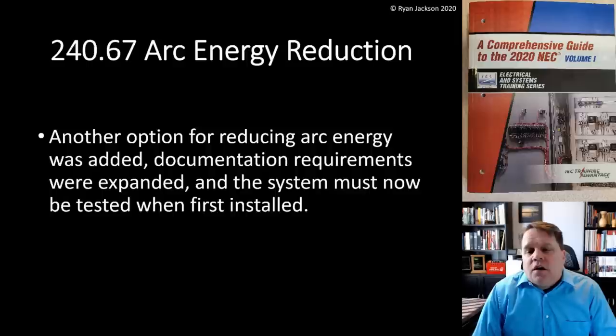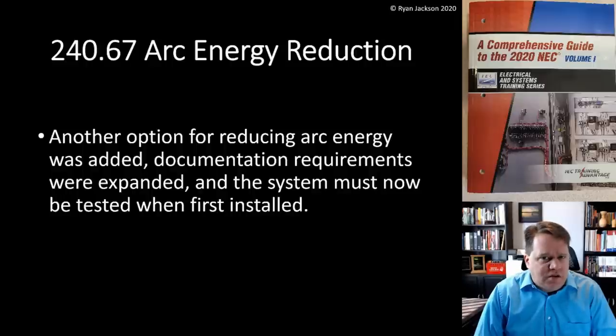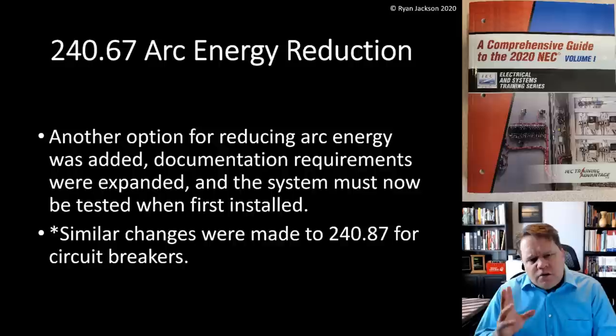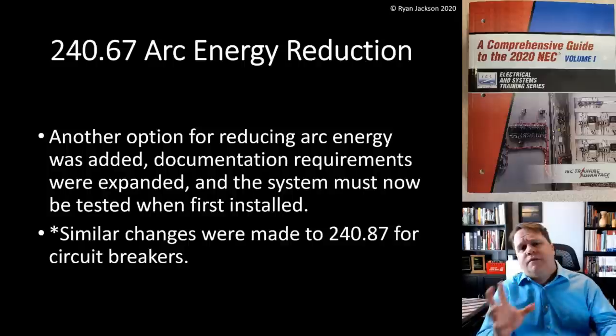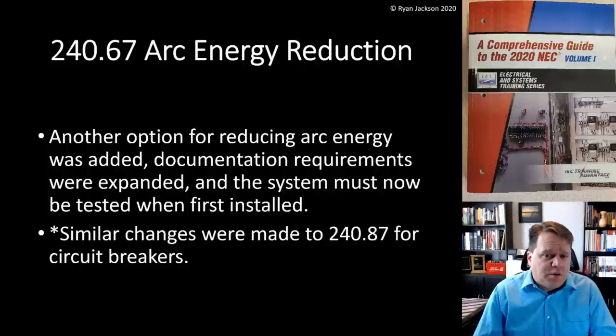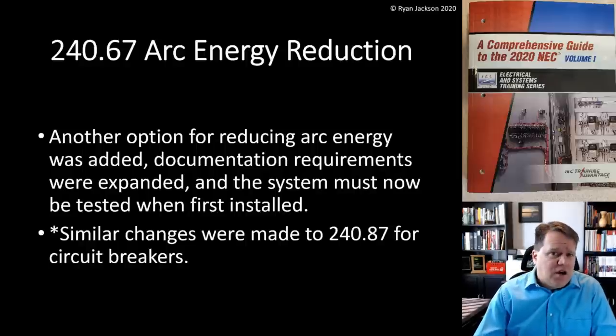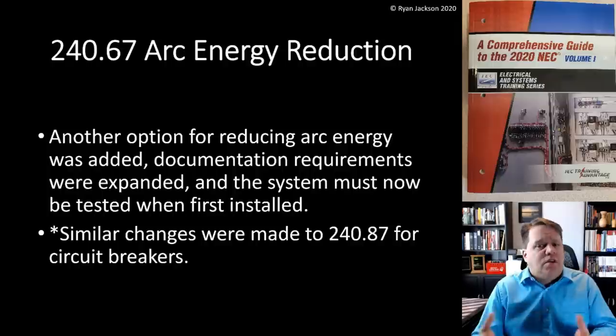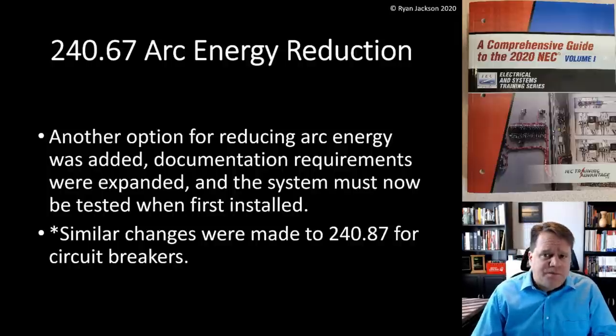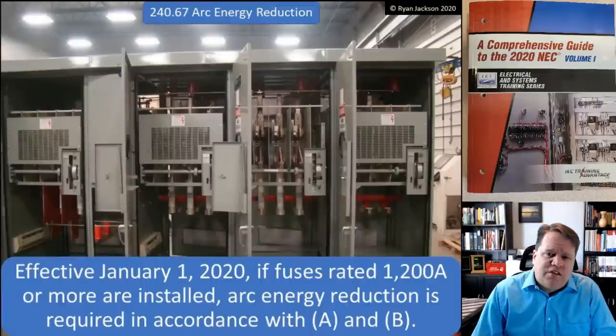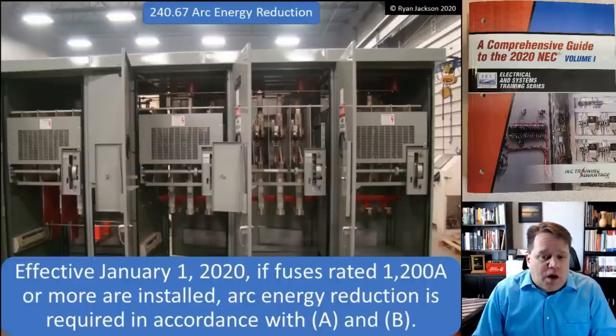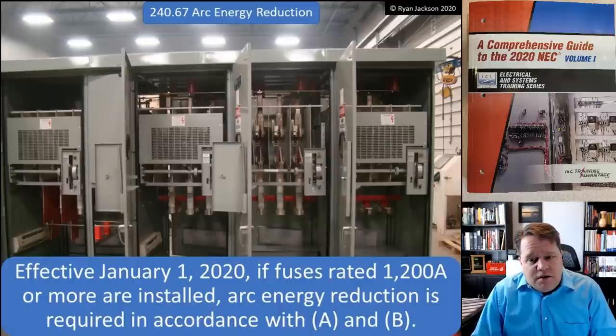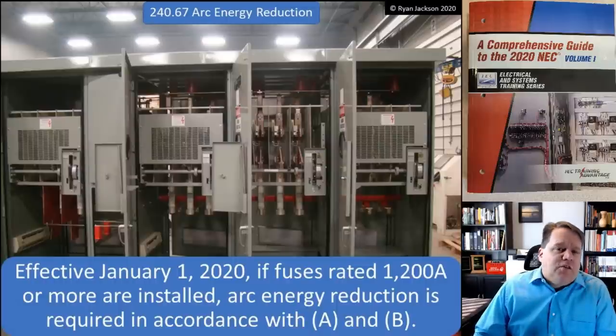Another change in Article 240 is to 240.67, Arc Energy Reduction. A new method for reducing arc energy was added, documentation requirements were expanded, and the system must now be tested when first installed. Note that 240.67 applies to fuses, while 240.87 has similar requirements for circuit breakers. The rule states: effective January 1, 2020, if fuses rated 1,200 amps or more are installed, arc energy reduction is required in accordance with items A and B.